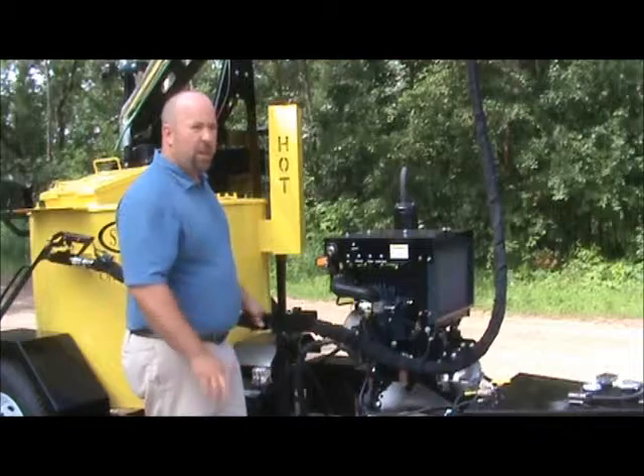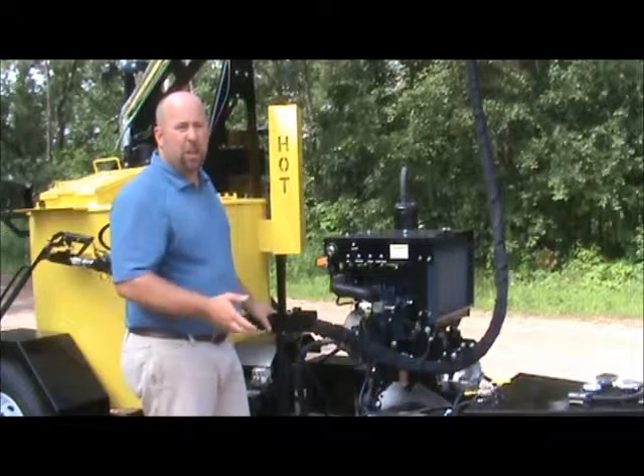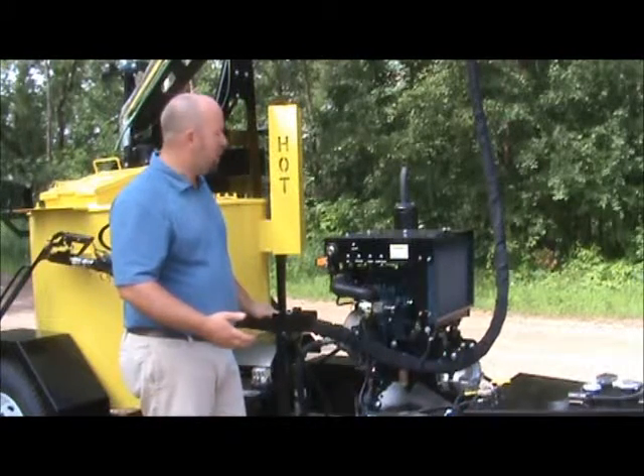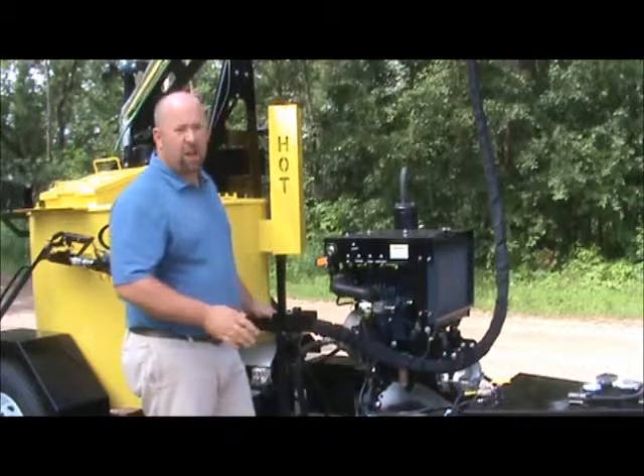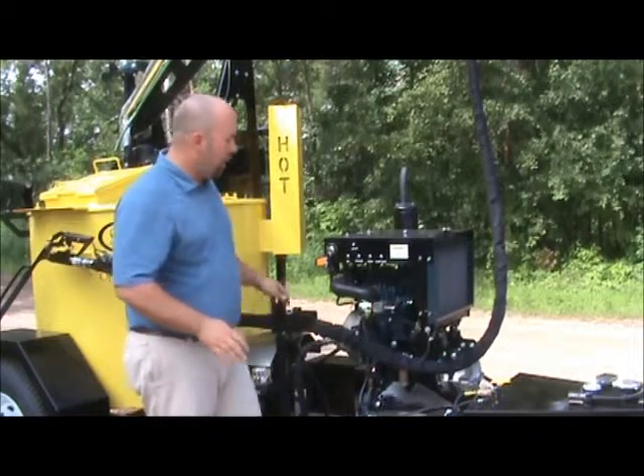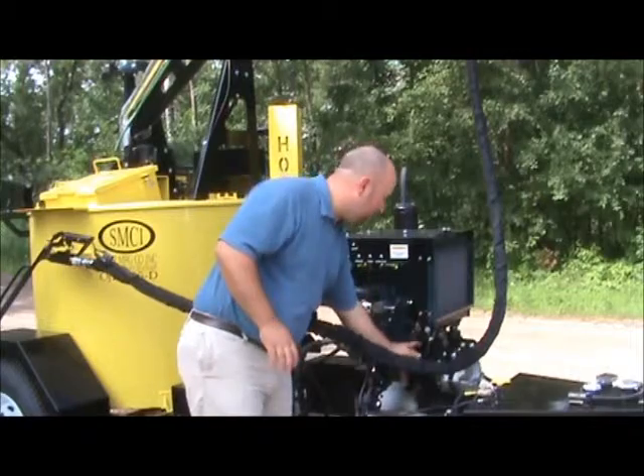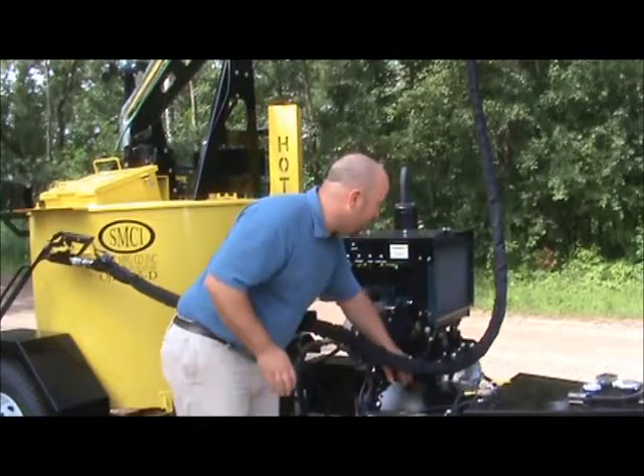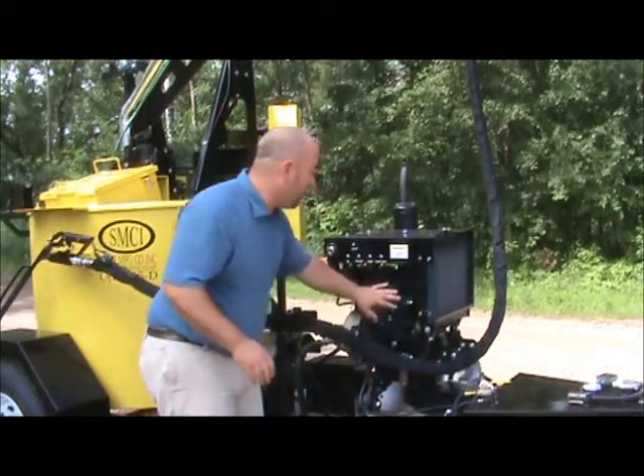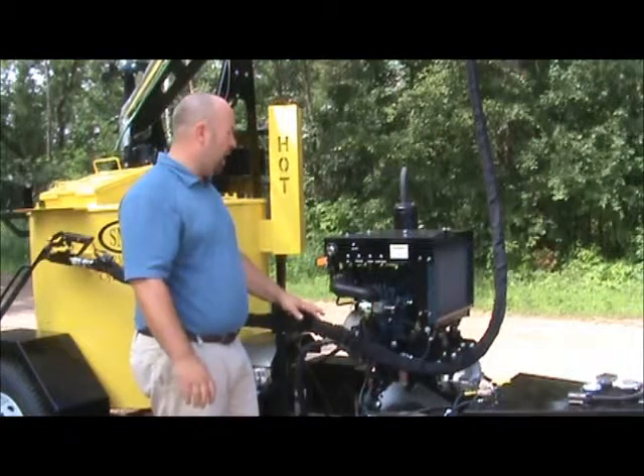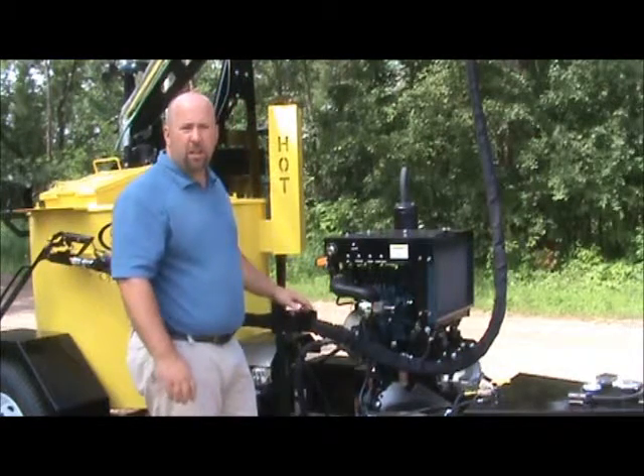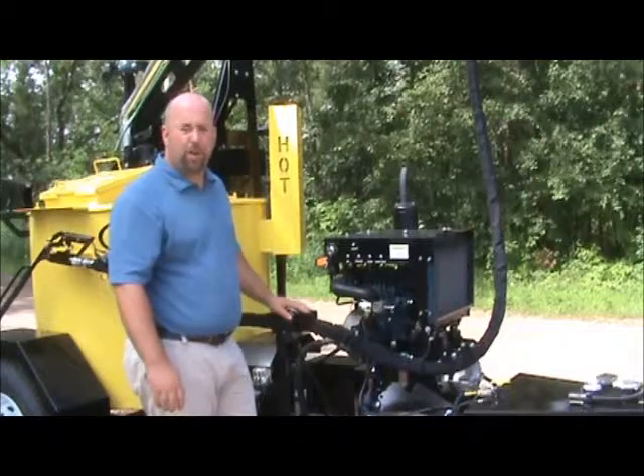One of the things we tell you to do on a new engine is to change the oil in the first 40 to 50 hours. After that, it's 100 hours on oil changes. When you do oil changes, check your belt tightness. You've got 3 belts on the unit, 2 that run the big alternator, and 1 that runs the small alternator and the fan. So those are some maintenance points there. When you change the oil, just make sure your belts are tight.